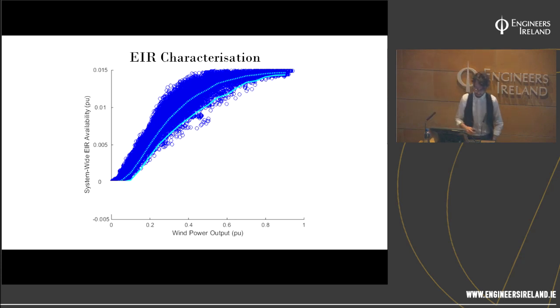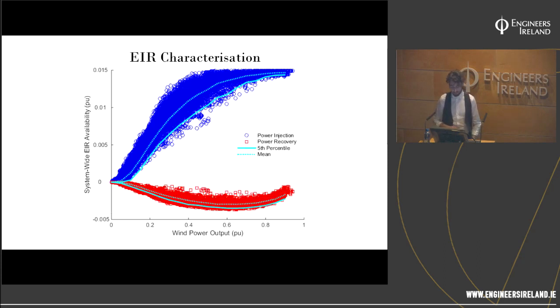If you're more, I suppose, some would say prudent, some would say risk averse, you could take the 5th percentile. So you're 95% guaranteed that at that wind power output, you're going to have an injection of inertial response greater than that. Of course, there's not just an injection involved with emulated inertia, there is a recovery period as well, which is probably important to characterize, because it might have a knock-on effect on your other reserve requirements if you have this draw of power.